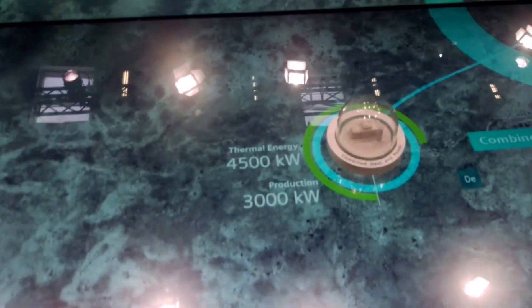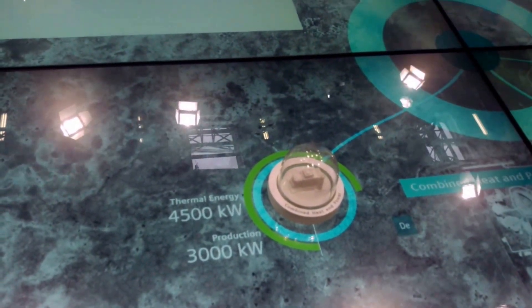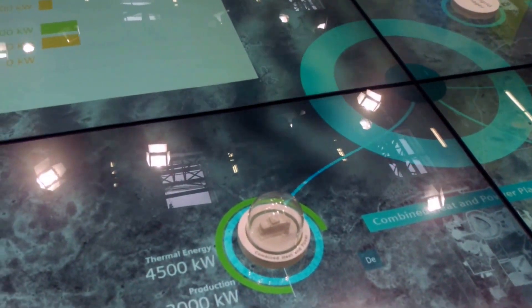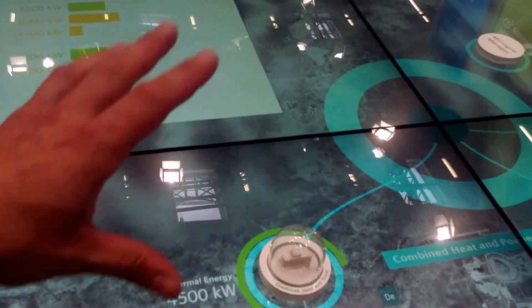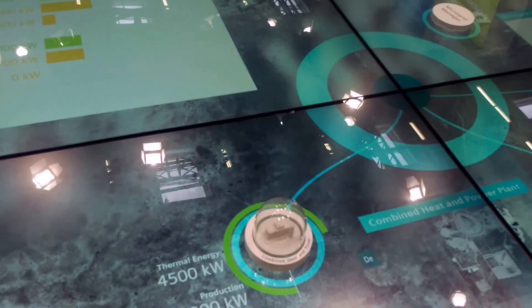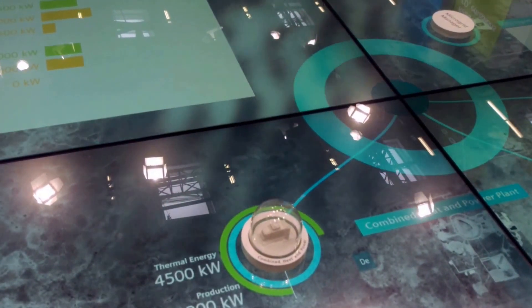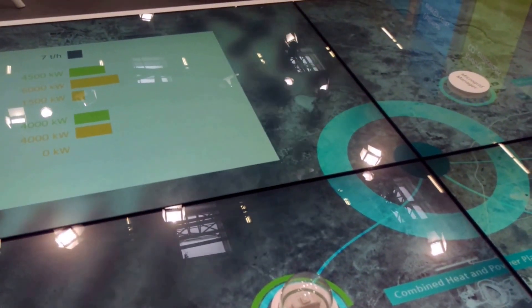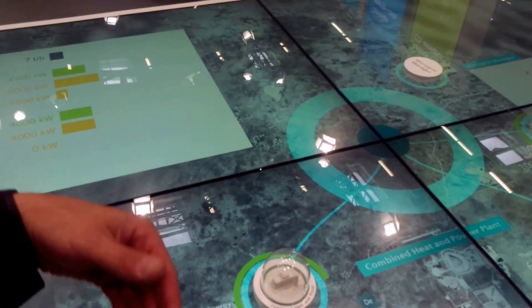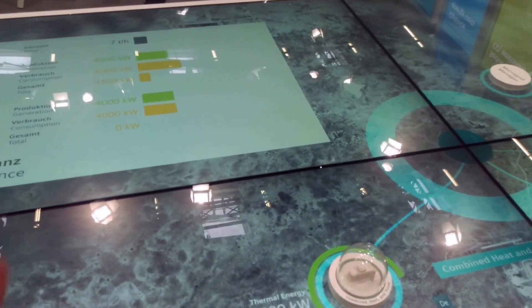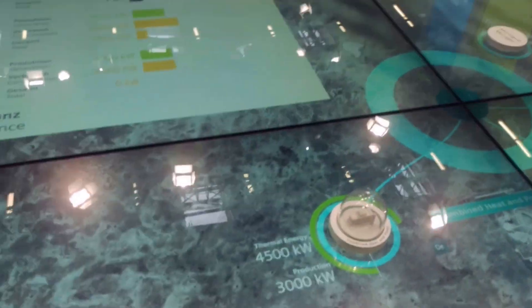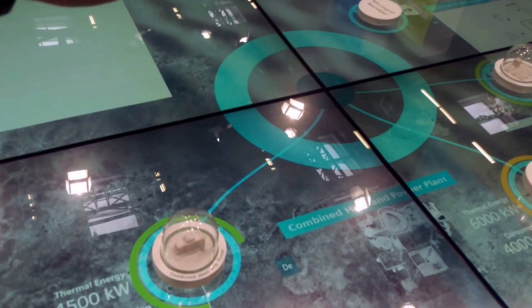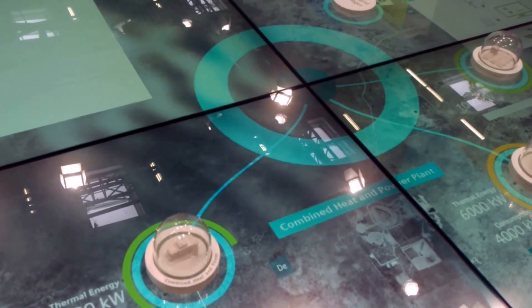Combined heat and power plants — what are they exactly? For example, a gas engine fired with natural gas. You can use not only the electric power but also the thermal power. A normal engine has about 30% efficiency, and on top of that, using the thermal power adds another 40% efficiency. Usually it's cooled by water, and you use that cooling water in the thermal process — that's a combined cycle approach. All of this is controlled by the microgrid manager or microgrid control system.